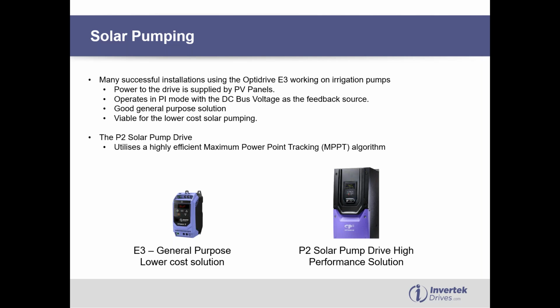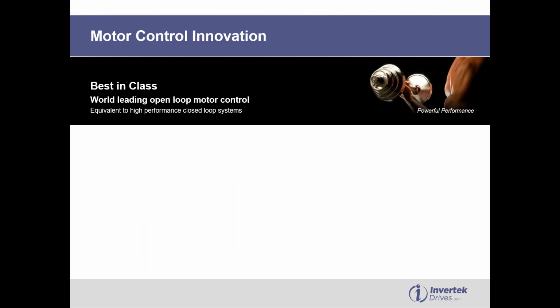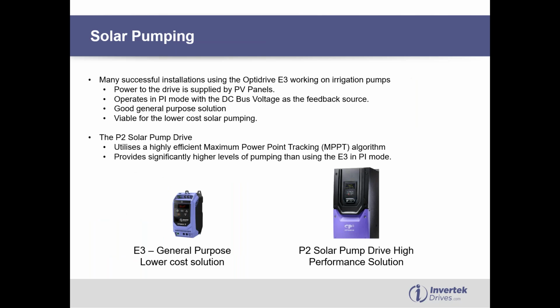We have special firmware in the drive which uses a highly efficient maximum power point tracking algorithm. So MPPT, anybody who deals with solar pumping will have heard the acronym MPPT, maximum power point tracking. It gives significantly higher levels of pumping than just using an E3 in PI mode. This is because it monitors the current conditions, like if there's clouds in the sky, what time of day it is. It monitors the actual power coming in from the solar array and regulates the pump speed much more accurately so that it utilizes as much of the power available.